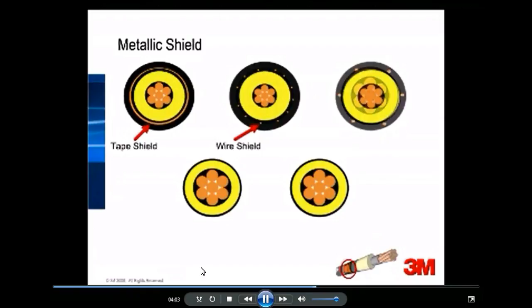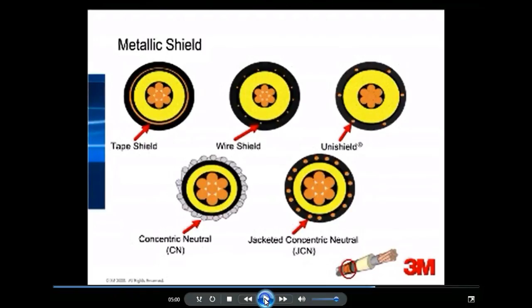Shown are common cable types. Tape shield cables fulfill the 6 different functions of a medium voltage cable in 6 different layers. Wire shield cables have the same basic construction as tape shield, and are often considered interchangeable with tape shield. Unishield combines the metallic shield, semiconducting layer, and jacket into one layer. This cable is designed to be very compact. Concentric neutral metallic shields also serve the function of a neutral conductor. Jacketed concentric neutral cable is basically the same as concentric neutral, except it has an outer jacket.